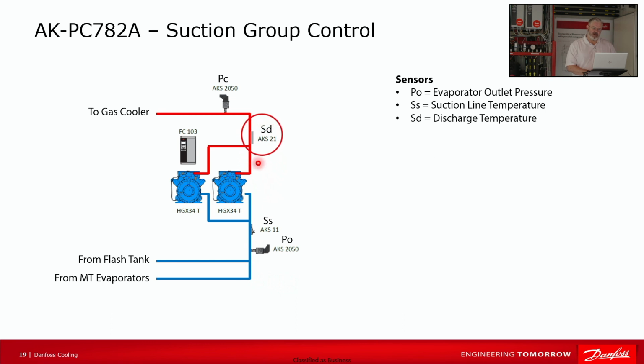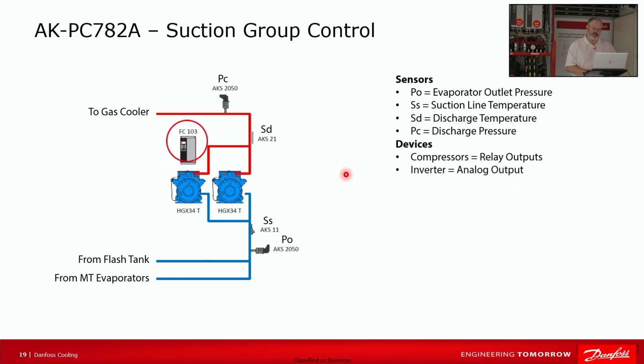Then for alarming and compressor safety, we have a sensor on the discharge line as well as a pressure transducer on the line to the condenser. So those are all inputs. We've used 4 inputs so far, all analog inputs. And then our devices are going to be our 2 compressors. So there's a couple of relay outputs that we're going to turn on and off. And then we'll have an analog output to send 0 to 10 volts to our inverter.